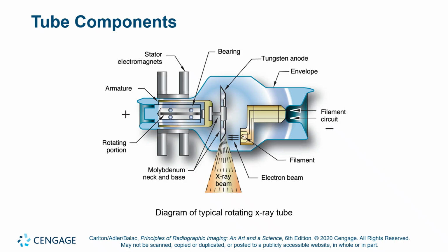Now the protective housing is not pictured here. It would go around all of this. The stator and the X-ray tube itself is inside the housing. The high voltage connections and the filament circuit connections also come into the housing. And there's a cathode and anode coupling that the housing brings in. So the housing starts as a cylinder, but it's got two exit points for the wires, usually on the back of the X-ray tube, facing back toward the crane. The electrons are excited at the filament once the filament gets hot enough. And then when the high voltage is applied, the huge positive charge that results on the anode pulls the electrons across at very high speed, up to, I think, 3/4 of the speed of light, 2.5 times 10 to the 8th meters per second.